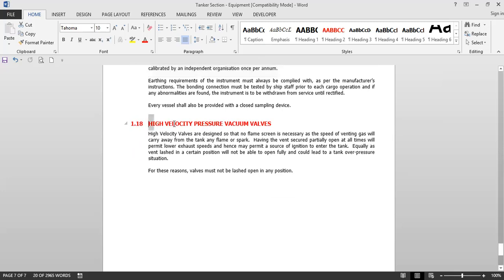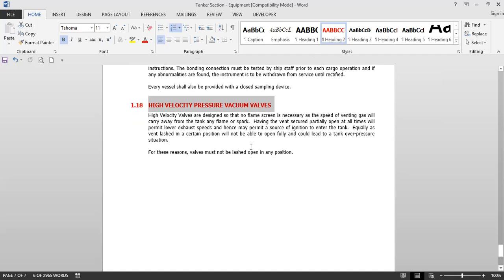High velocity pressure vacuum valves are somewhat similar to PV valves. High velocity valves are designed so that no flame screen is necessary, as the speed of venting gas will carry away any flame or spark from the tank. However, if a vent is lashed partially open, it will permit lower exhaust speeds and may permit a source of ignition to enter the tank. Similarly, a vent lashed in a certain position will not be able to open fully and could lead to a tank over-pressure situation. For these reasons, valves must not be lashed open in any condition.